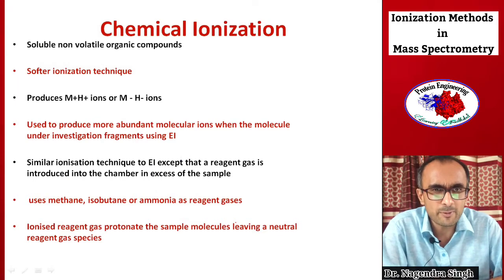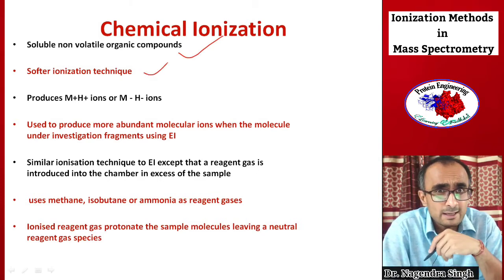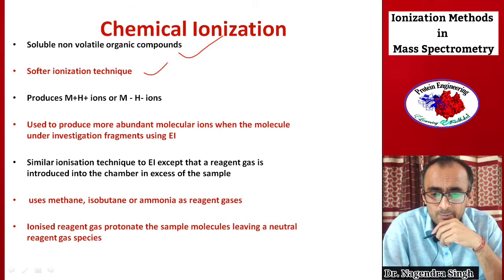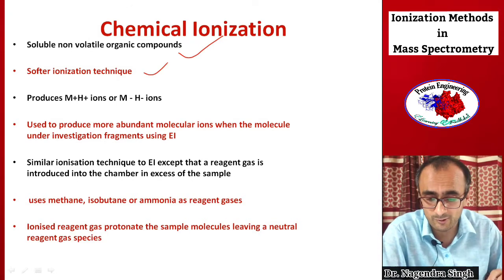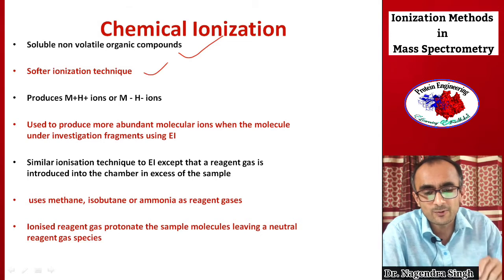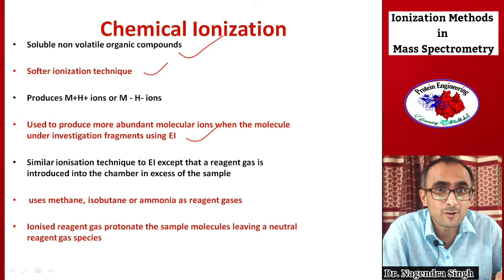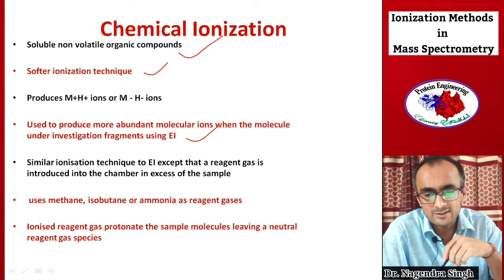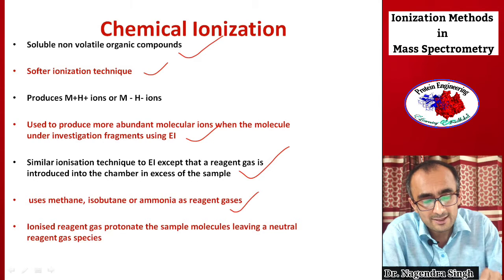Chemical ionization is also used for volatile organic compounds and is a softer ionization method than electron impact. It produces charge on the analyte by protonation or deprotonation — by addition or removal of a proton — and produces more abundant molecular ions. It can be used to reduce the heavy fragmentation seen with EI. It is very similar to EI except a reagent gas — such as methane, isobutane, or ammonia — is used in the ionization chamber.